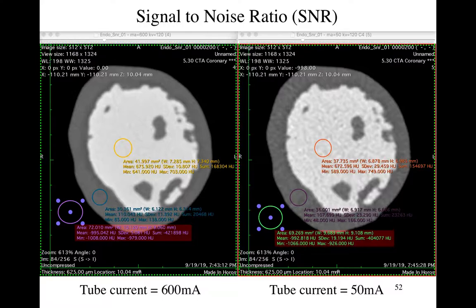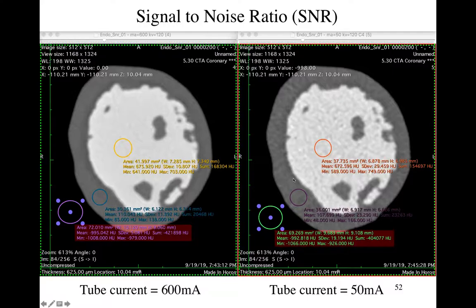It gets complicated in X-ray imaging because the noise here is actually different from the noise there. You have to pick — maybe the average noise or some other definition. When you have high-intensity pixels in CT, that means the photon attenuation was greater. A contrast agent attenuates more photons, so the detector saw fewer photons making that part of the picture. When you have fewer photons, the uncertainty in the count goes up, so noise changes depending on the value of the material.